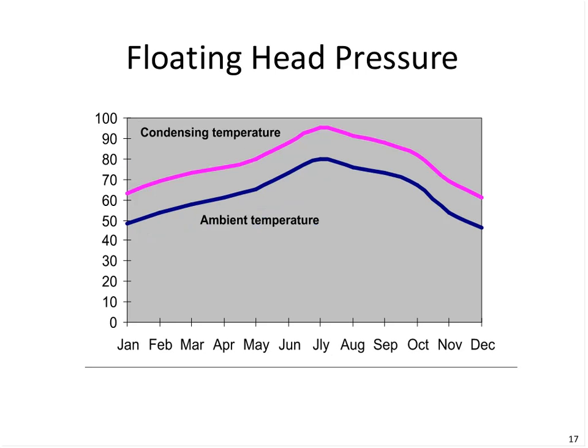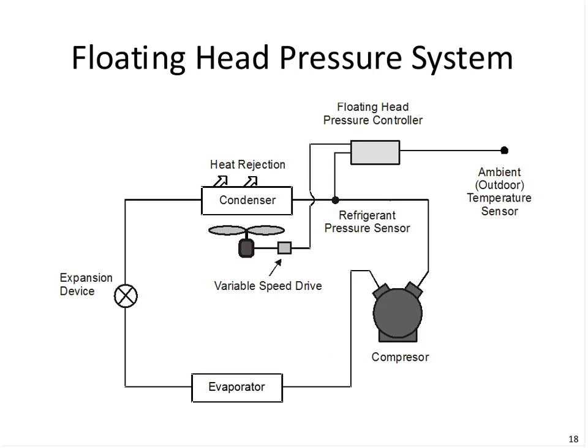Floating head pressure is indicating that we're adjusting the set point so that when we're at an ambient of around 50, then maybe we're condensing at 60, 65, and taking advantage of those lower ambient conditions. Of course, on a hot day, all the fans in the condenser are probably running full speed. We're doing the best we can to keep up with the heat gain.